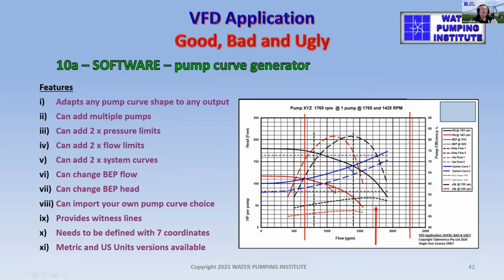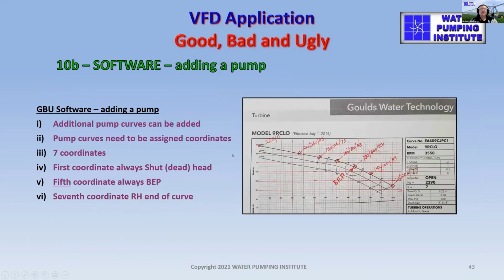You can add 2 pressure limits, 2 flow limits, as we're seeing. There are 2 system curves. I'll go back to the software in a moment and show you a couple more features. To add a new pump curve to it, you print off a pump curve from a family of curves and identify 7 operating points on the curve, and note the coordinates and simply add the coordinates into the Excel matrix. It's important that the 5th one, starting from 1, 2, 3, 4, 5, the 5th one is always at the BEP, best efficiency point, and I'll demonstrate why in a moment.